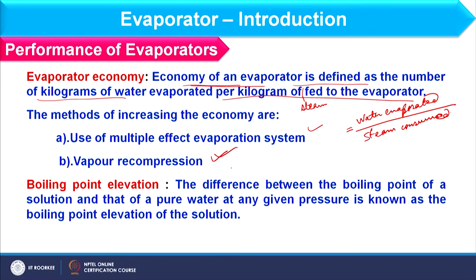We also consider boiling point elevation in evaporators. When a solution contains some other component — an impurity — the vapor pressure reduces compared to the pure solvent. More heat is required for the desired evaporation, so the temperature of the solution increases compared to that of the pure solvent. The difference between these two temperatures gives the boiling point elevation. This will be further discussed in subsequent lectures.